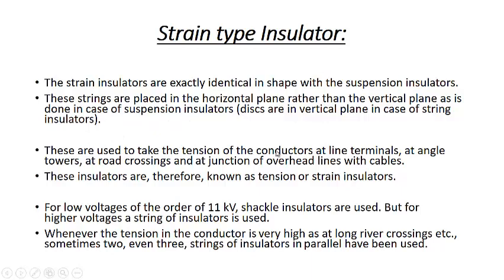These are used to take the tension of the conductors at the line terminal, that is the dead end, at angle towers when the transmission line is bent, at road crossing, and at the junction of the overhead line with cables. Junction means when there is more than one transmission line at any pole which are connected to each other. At that time also we use the strain type insulators. These insulators are therefore known as tension or strain insulators because they carry tension as well as strain. For low voltage of the order of 11 kV, shackle insulators are used, which I have already told you. But for the higher voltage, string insulator is used.